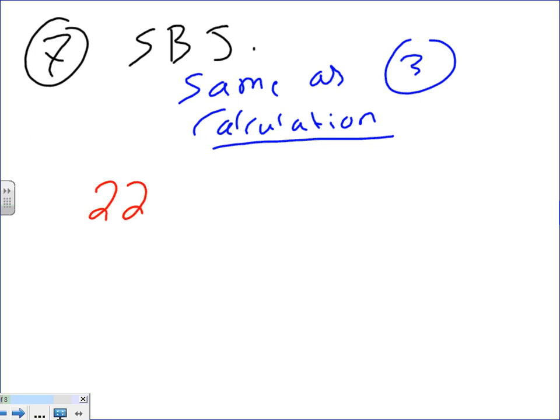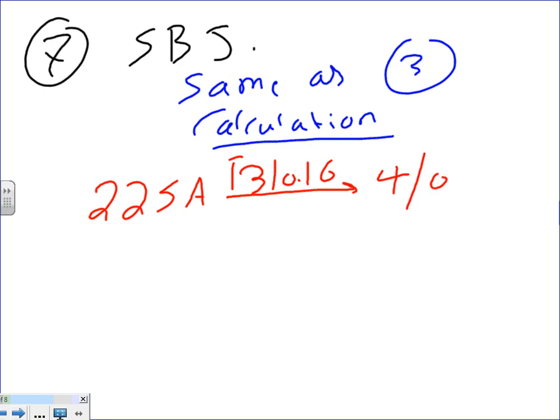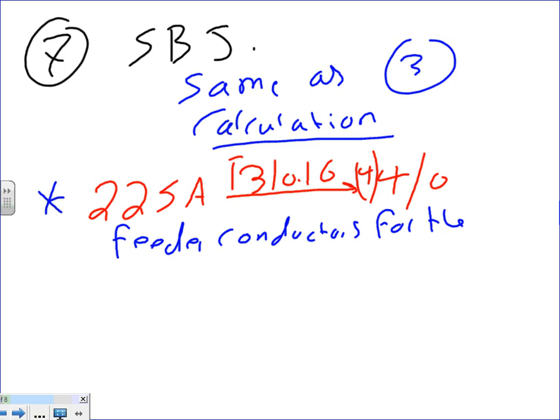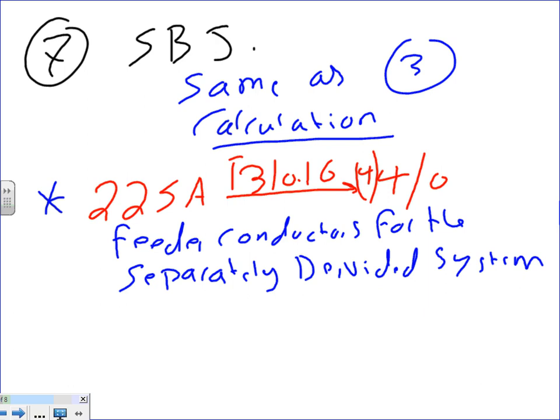So Spencer, I have 225 amp. I need to size the conductors for 225 amp. 310.16, table 310.16, size the conductors for this panel. So number 7, I need to size the conductor for this panel. Says system bonding jumper. So what is it, 4-aught? 4-aught? Okay. So I have conductors 4-aught. How many? I need 4. The first thing, guys, this is the first thing I size right here, as feeder conductors for the separately derived system, right? I have a 225 amp panel. I just sized the feeder for it.